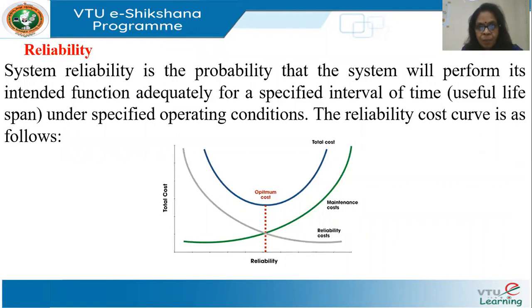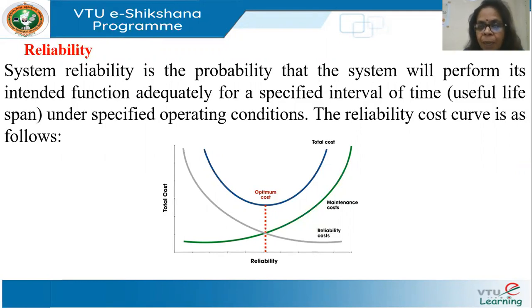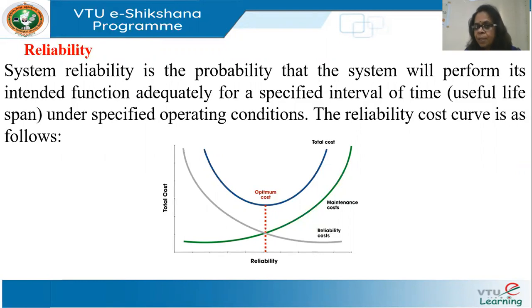When it comes to reliability, in the power system context it has two meanings. One is adequacy — that is, how adequate is it? Is my supply able to meet the demand? The second is security. To build this adequacy and security, we have to invest money because we have to build redundancy. If my demand is 10,000 megawatt and I have generation exactly 10,000 megawatt, then I'm not prepared — I don't have any reserve.